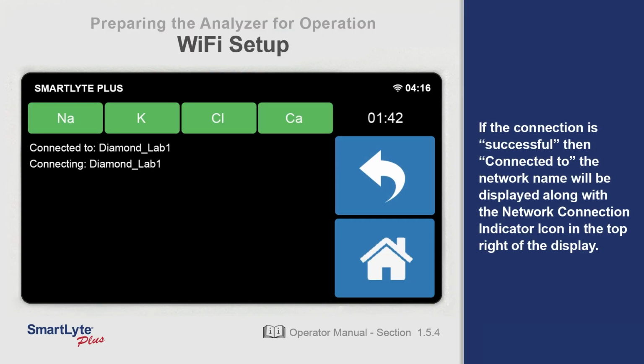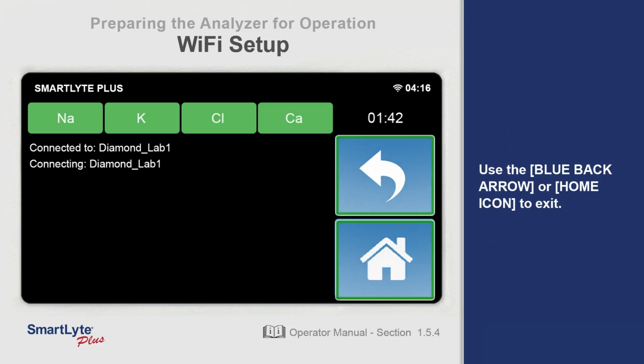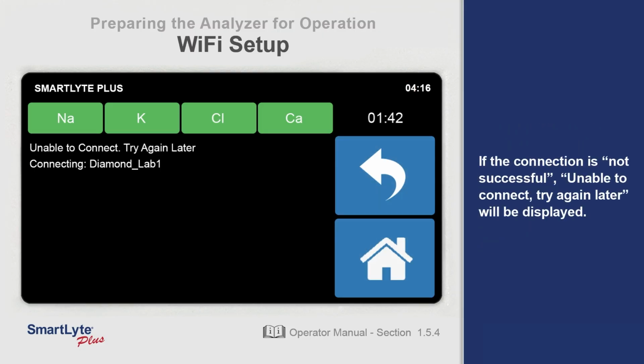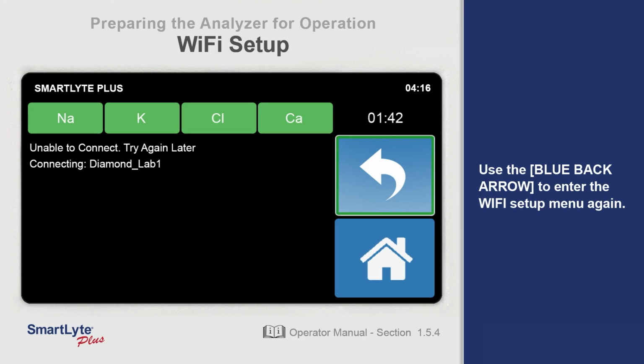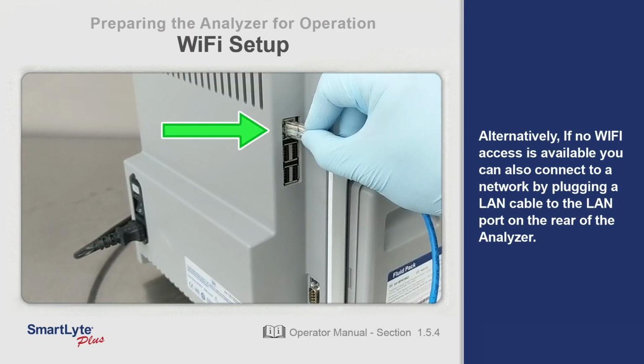If the connection is successful, then "Connected to," the network name, will be displayed along with the network connection indicator icon in the top right-hand corner of the display. Use the blue back arrow or home icon to exit. If the connection is not successful, "Unable to connect, Try Again Later" will be displayed. Use the blue back arrow to enter the Wi-Fi setup menu again. Alternatively, if no Wi-Fi access is available, you can also connect to a network by plugging a LAN cable into the LAN port on the rear of the analyzer.